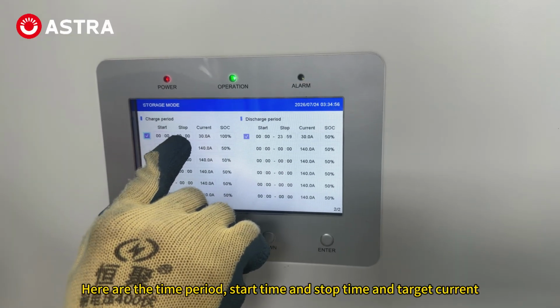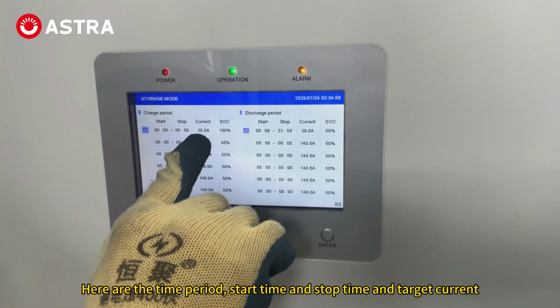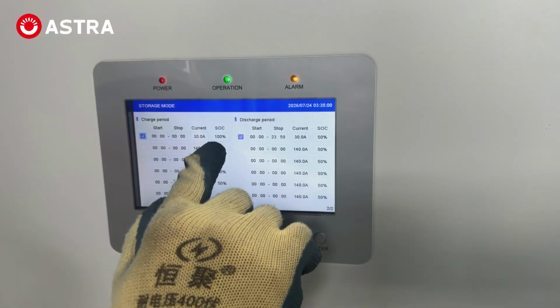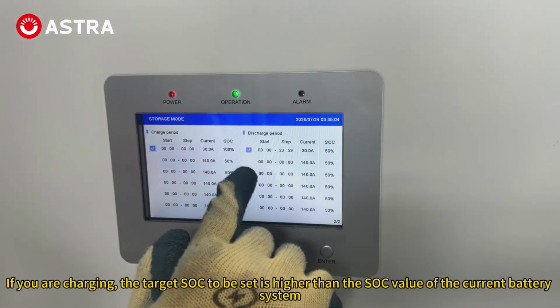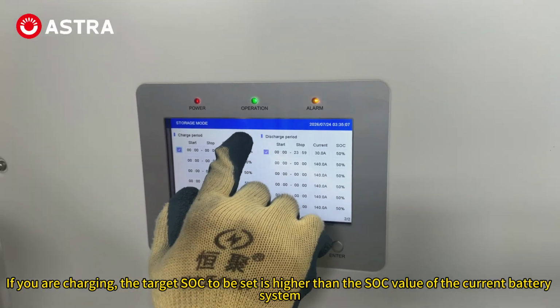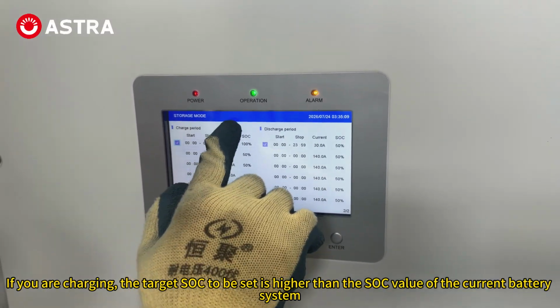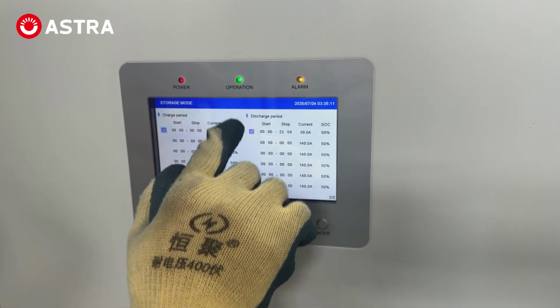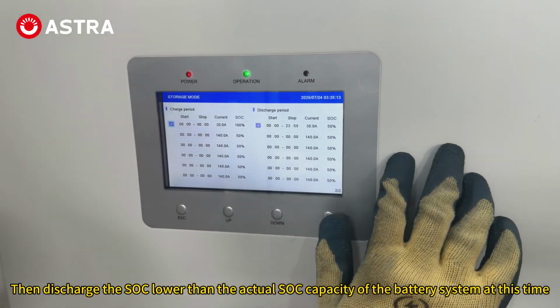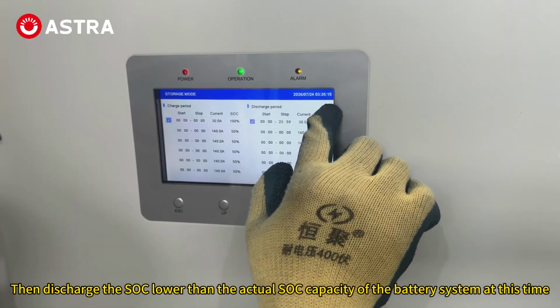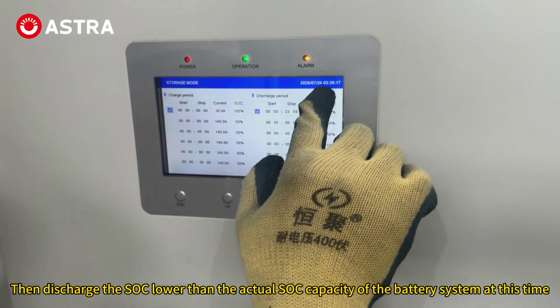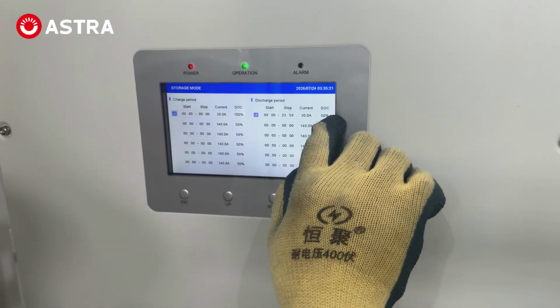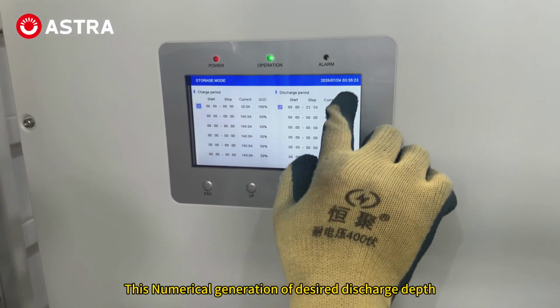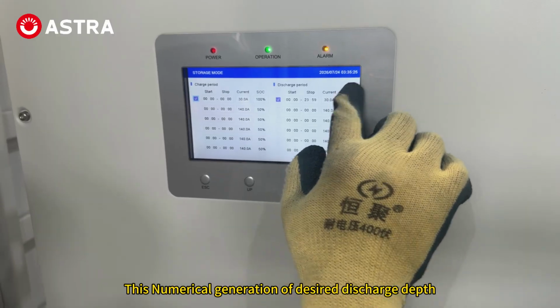Here are the time period, start time and stop time and target current. Then the SOC. If you are charging, the target SOC to be set is higher than the SOC value of the current battery system. Then for discharge, set the SOC lower than the actual SOC capacity of the battery system at this time. This numerical value determines the desired discharge depth.